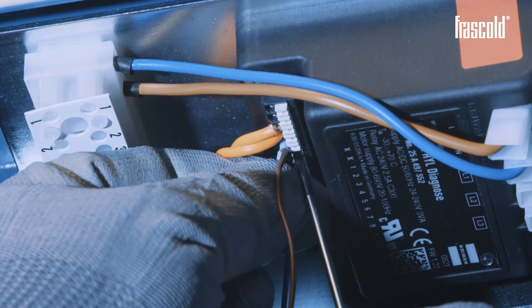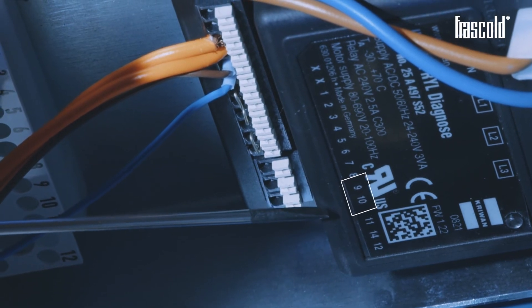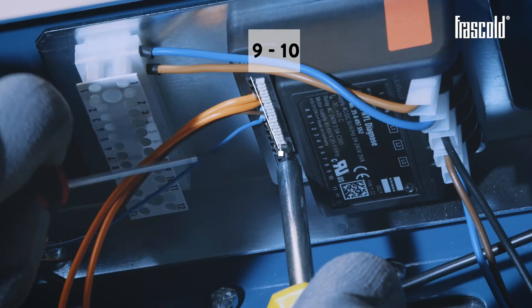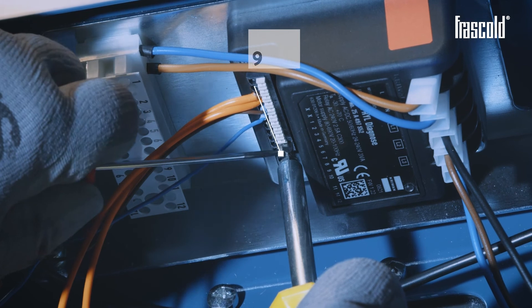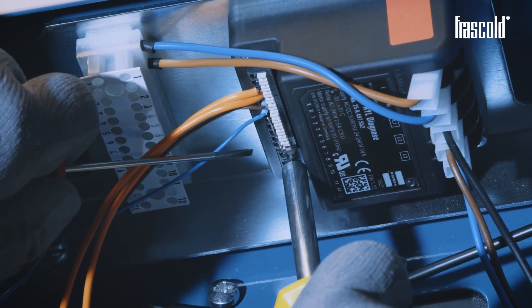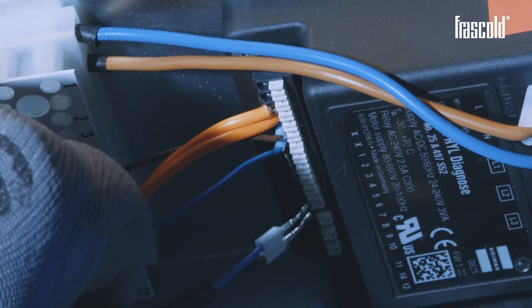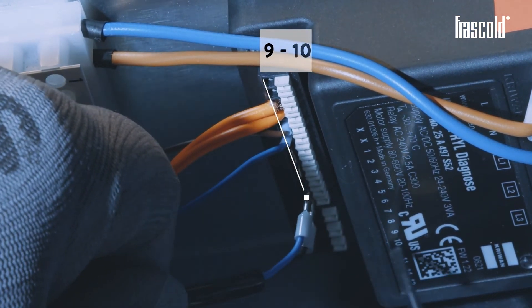To proceed with the wiring of the flow switch, remove the jumper on the KRIWAN Diagnose device from inlets 9 and 10, and, using two slotted screwdrivers, insert the two flow switch cables in its place.